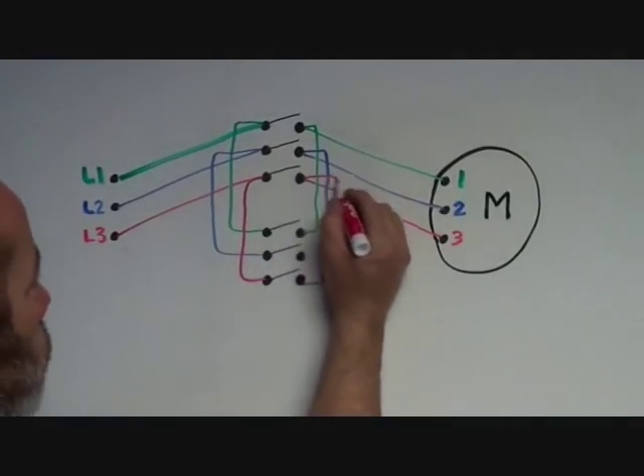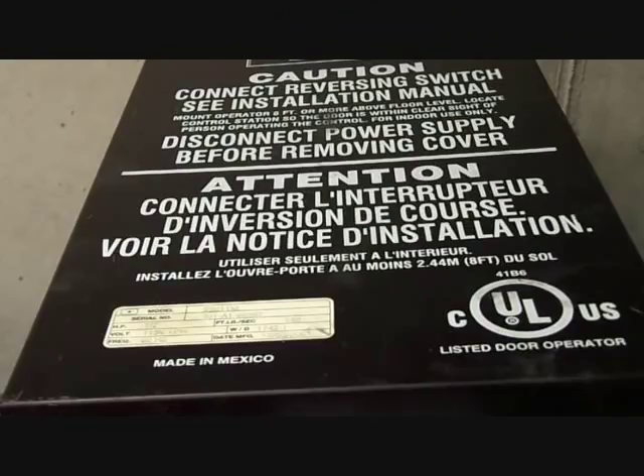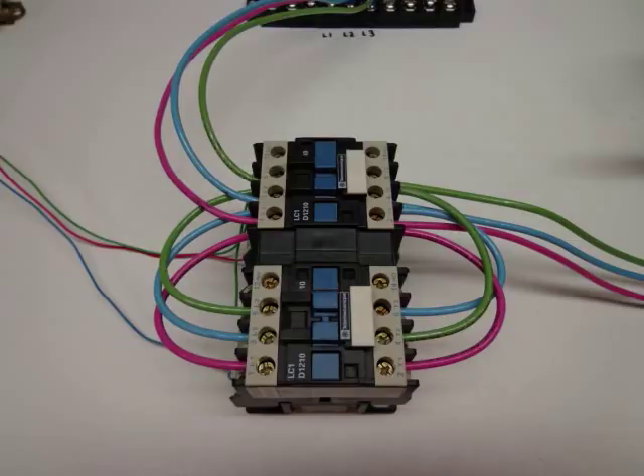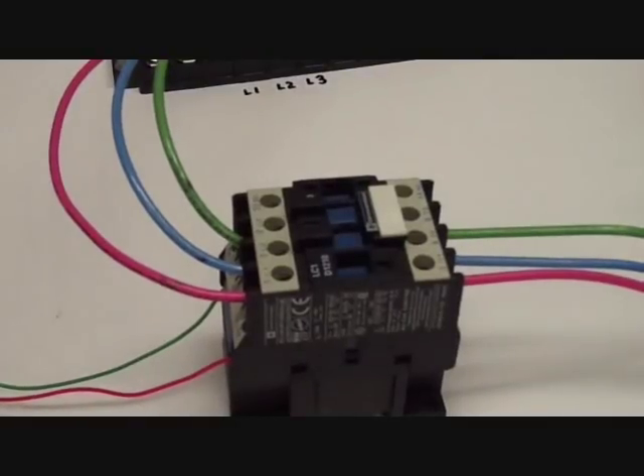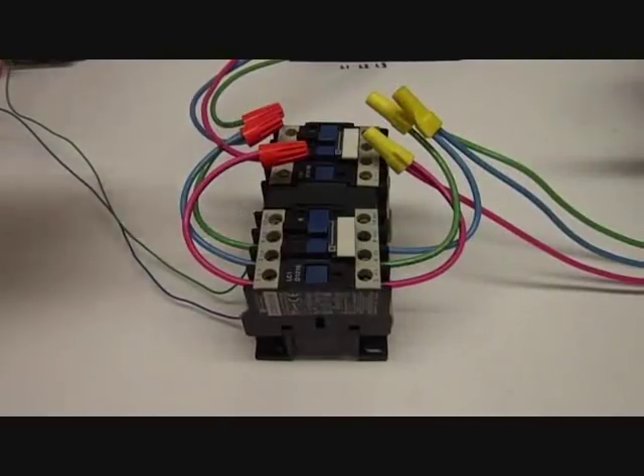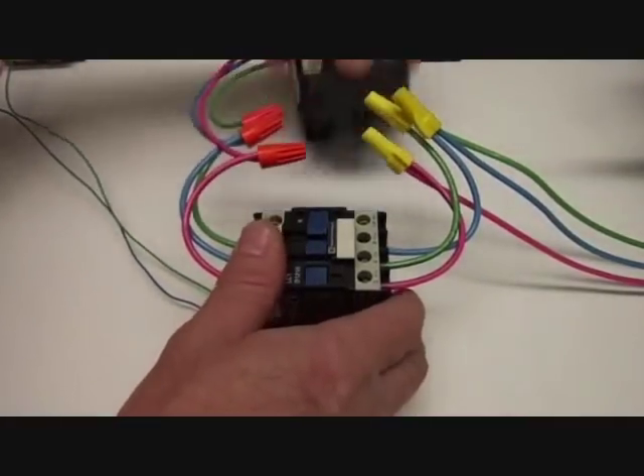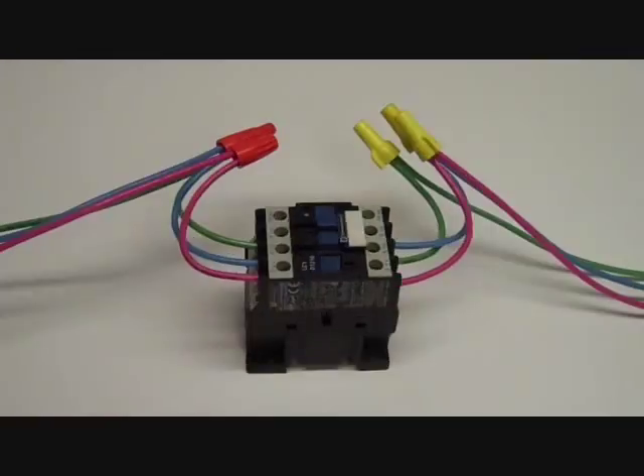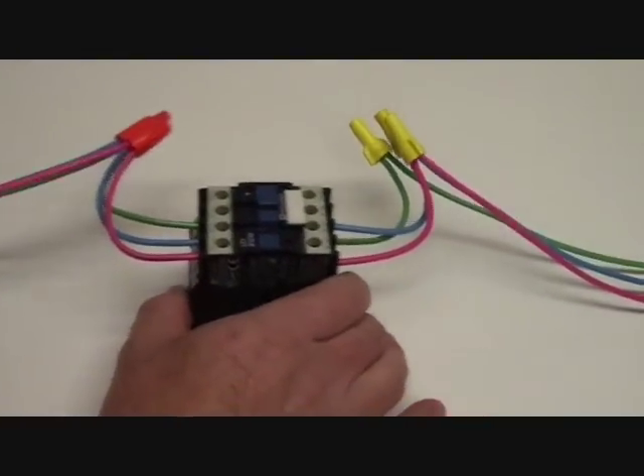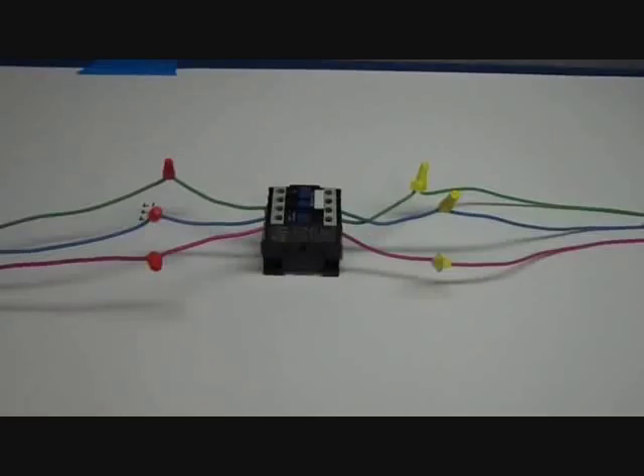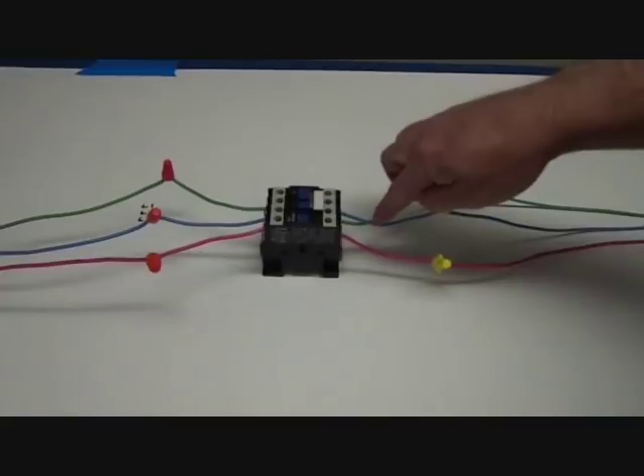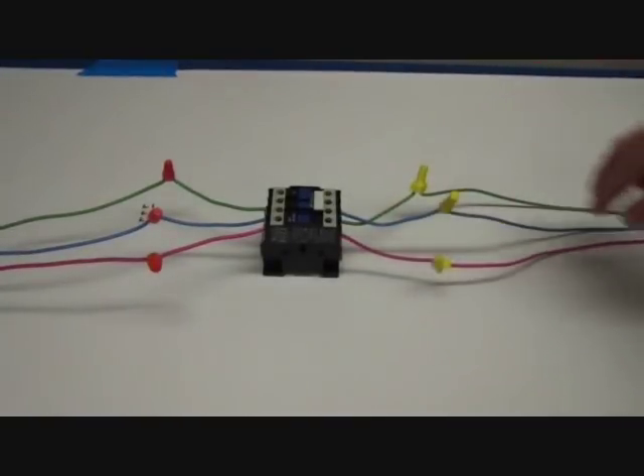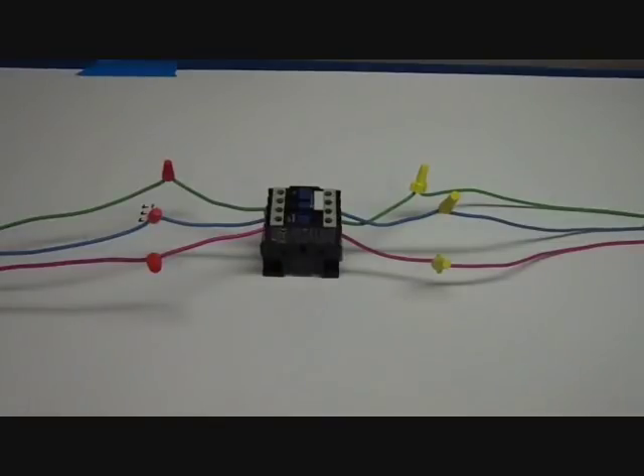Now it looks pretty complicated, a lot like the tangled web of wires you see inside these machines. But if you just look at the first contactor and ignore all the jumpers, you can see that when the coil is energized, the three wires from the power supply go straight to the motor terminals. For the other direction, it's much easier to imagine that the clockwise contactor doesn't even exist, and that there's just some terminals that connect the wires together. And when I spread it out, it hopefully makes even more sense. You've got your three phases coming into lines one, two, and three, and then they come out and go directly to the motor, but with two and three swapped.